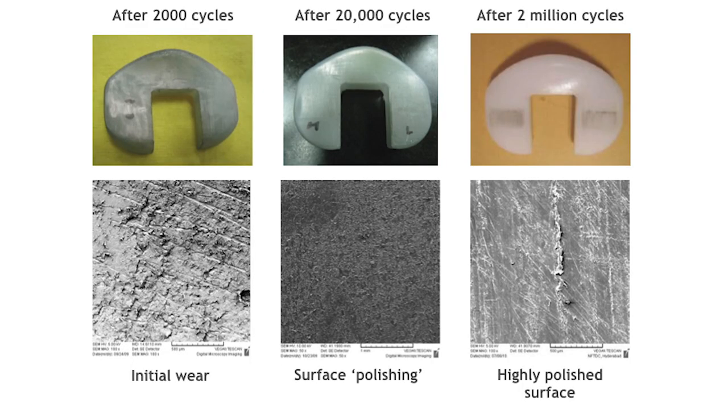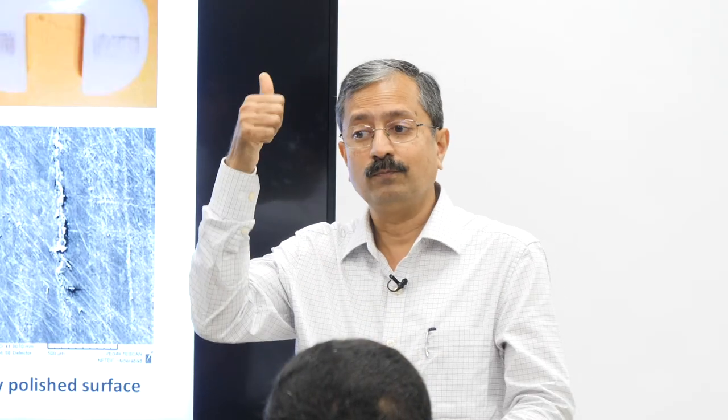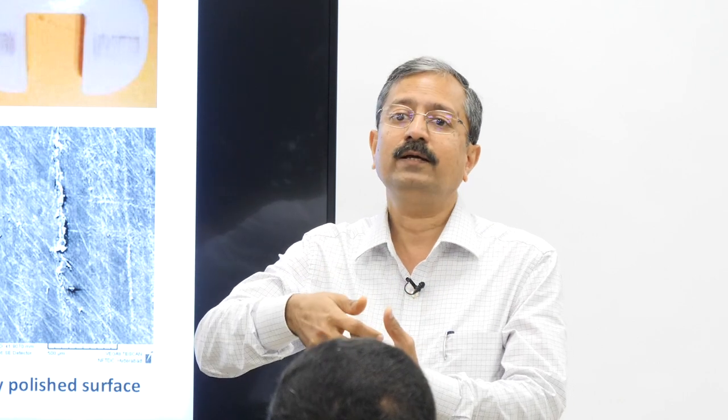This polymer part — let me tell you about the materials of the joint. Stainless steel is bio-inert: neither friendly nor an enemy. But the bio-friendly material is titanium. If you make titanium with the right surface finish, the bone literally grows onto the titanium parts and grips it very nicely. So the stem portion which goes into the bone is titanium. But titanium is very poor in wear resistance. Where you have moving parts and therefore wear, you can't put titanium. So where the movement is, you put a cobalt chromium molybdenum alloy — highly strong and highly wear-resistant, but much heavier than titanium. Fortunately that part doesn't go into the bone; titanium goes into the bone. So you use cobalt chromium molybdenum alloy where movement occurs.